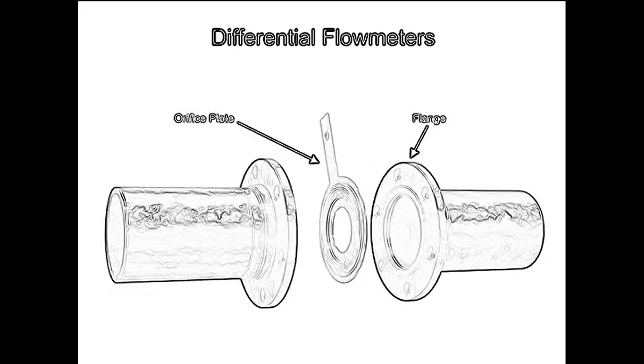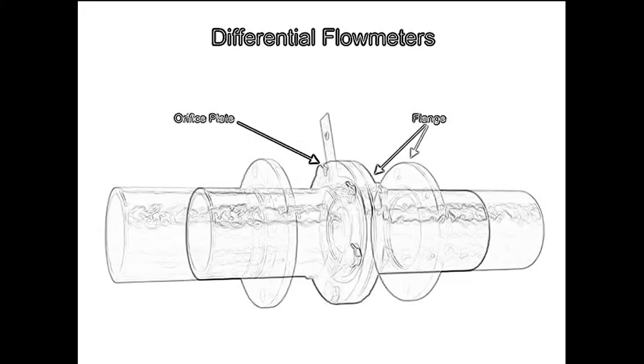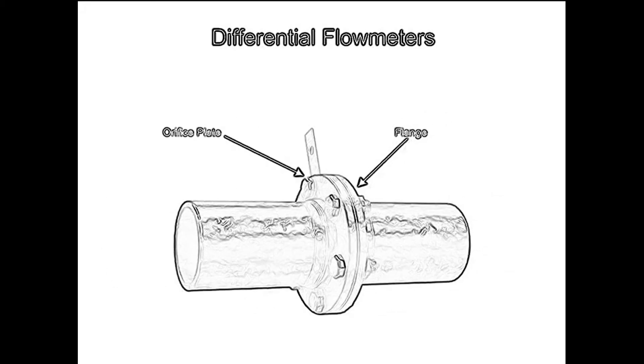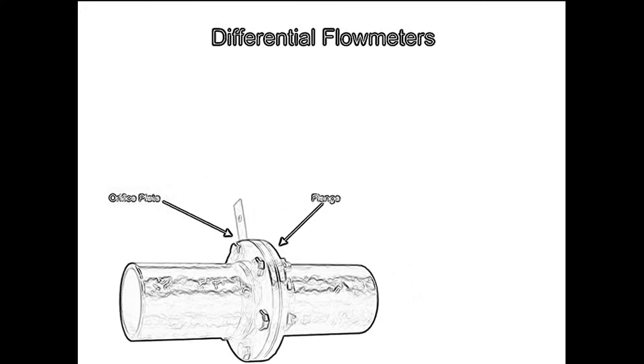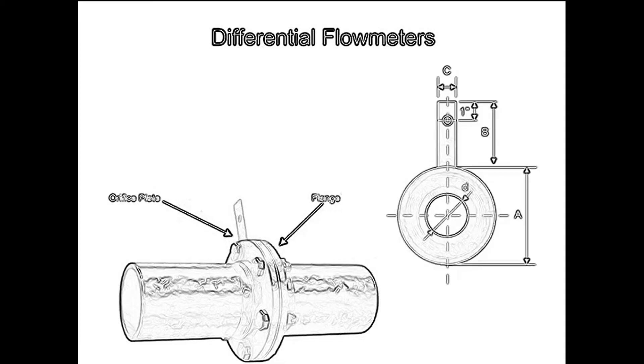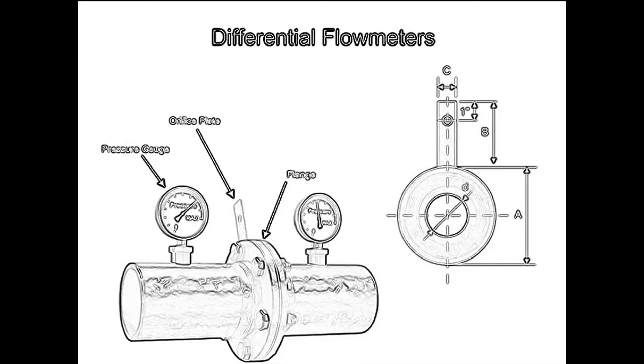Whether venturi tube, flow nozzle, or orifice plate style, the differential flowmeter is an inline instrument installed between two pipe flanges. The orifice plate is comprised of a circular metal disc with a specific hole diameter that reduces the fluid flow in the pipe. Pressure taps are added on each side of the orifice plate to measure the pressure differential.